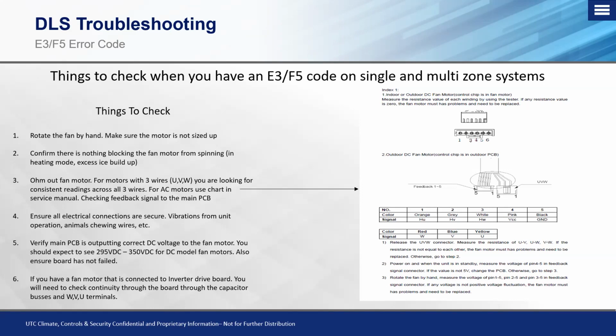So we're doing 1 through 5, 2 through 5, and 3 through 5 to make sure that we're getting a certain amount of voltage feedback through the signal connector. If any of that voltage is not a positive voltage fluctuation, similar to what we see with the L2 and the S terminals when we're checking communication, so you're getting a negative to positive, the fan motor has an issue internally with the signal feedback, and it needs to be replaced.